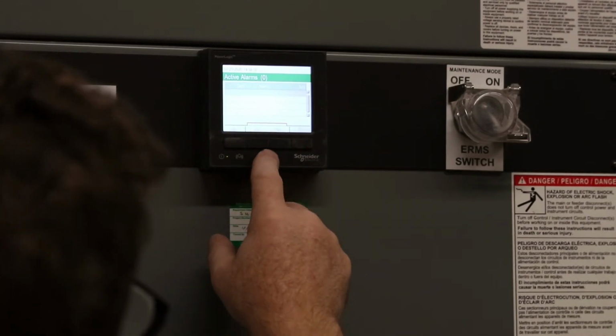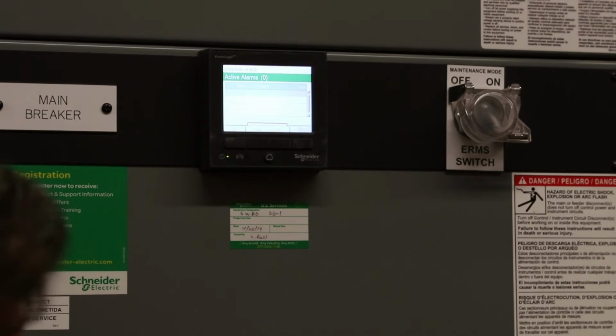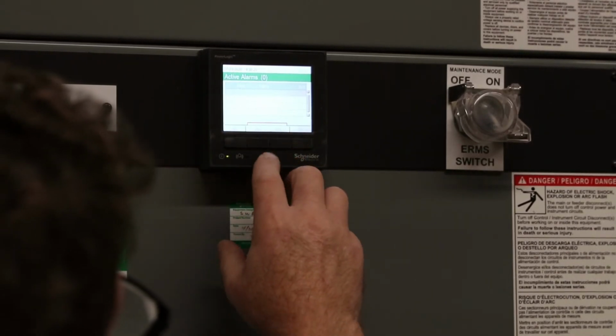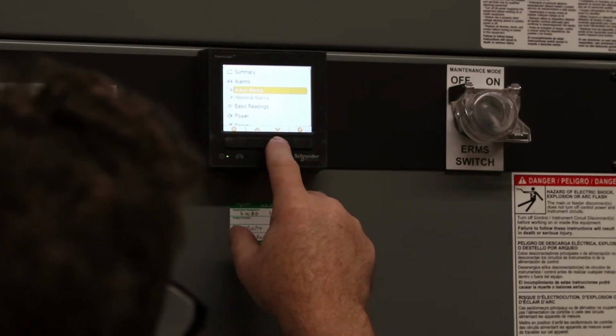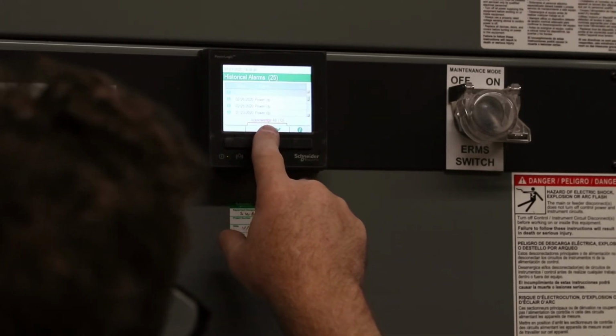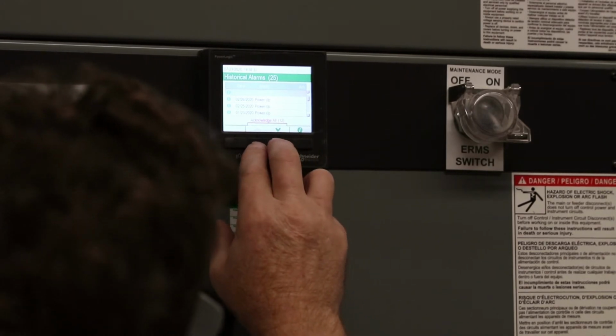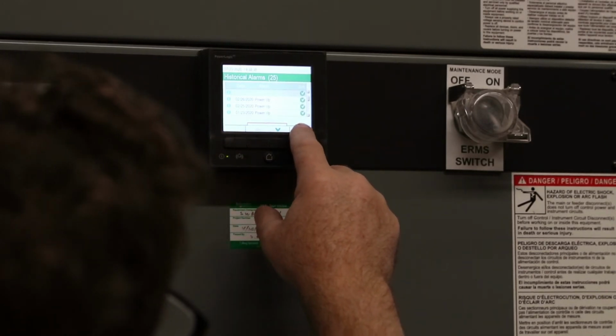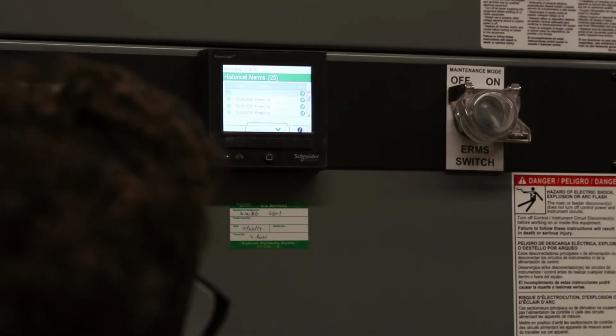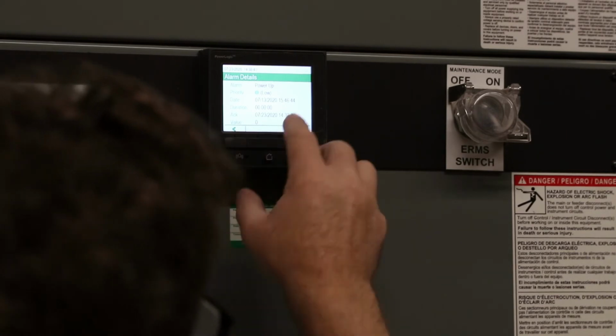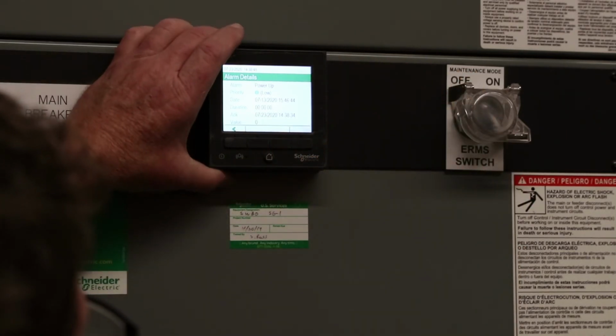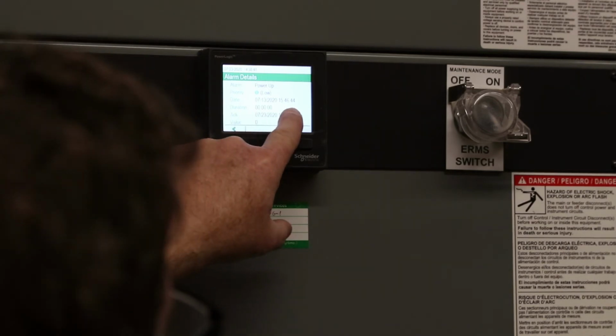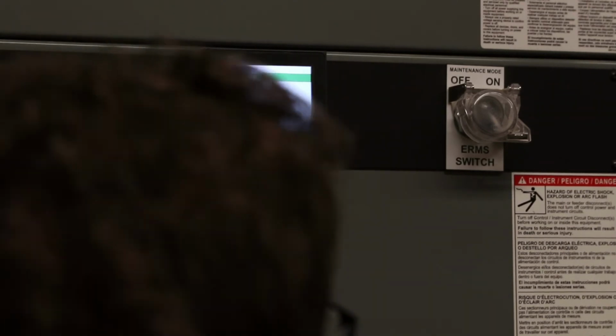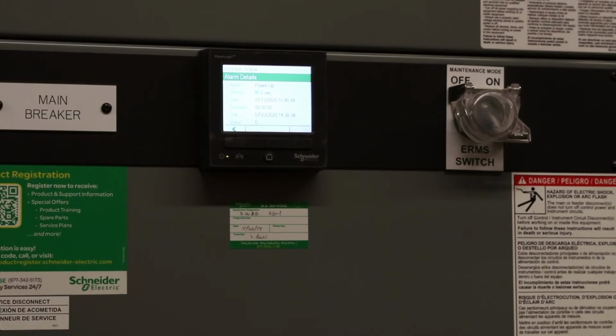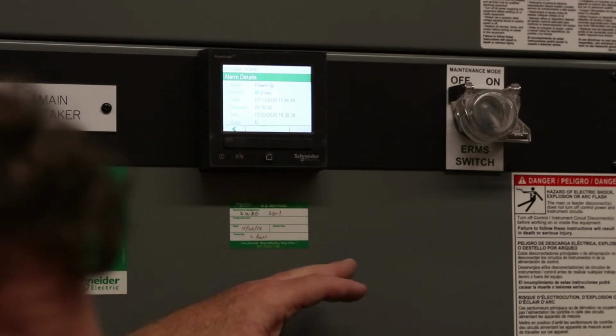No active alarms. If you had an alarm, under voltage or sag, and you wanted to clear it once it's corrected, you go to historical alarms, enter, acknowledge all. Those show as all acknowledged, and hit enter. They were already acknowledged, so it didn't do anything, but you can go to the alarm and get all the detail: date, time stamp, and what it was. If you're going through software, you can pull up a waveform capture to show what exactly happened to generate that alarm. You can't really get the waveform capture through the faceplate.